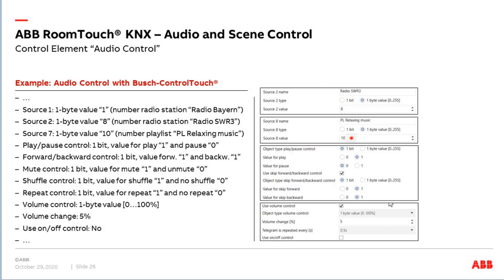I don't want to use on/off, and play/pause as one bit: value one for playing and value zero for pause. For backward with value one I go backward, and with value one for a separate object I go forward — using two different group objects. I also want to control the volume with a range from 0 to 100%, and every time I press the plus or minus button we send a new value of plus 5%.